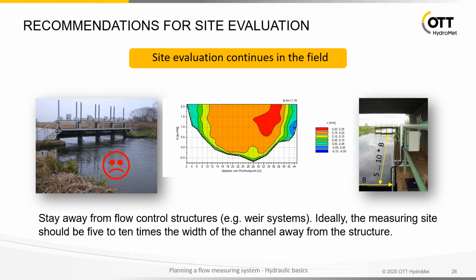And if you have set up a surface velocity radar somewhere downstream, then you are not measuring in the area of the maximum flow. If you have a side-looking Doppler, also here the index ratio will be unstable, because depending on how they regulate the weirs, the velocity distribution will change across the river. And that's why, stay away, and ideally the measuring site should be 5 to 10 times the width of the channel away from the structure.